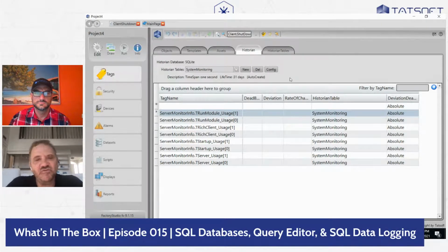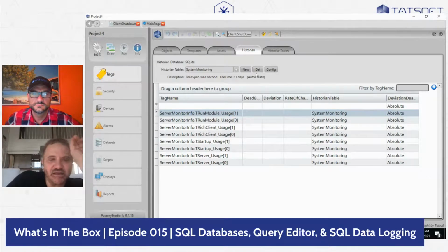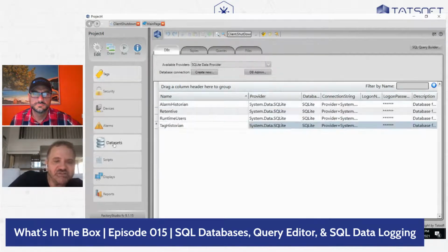And it's very hard to give you a magic number because it depends on how you do your configuration and the hardware. You can get amazingly different numbers on that. So I give you the principles, but not exact numbers. So what should you be aware of? When you do data logging using our own tool, first of all, you have the ability to select where you are going to log. SQLite is good for small projects, a few hundred tags. When you start to go to thousands, you should think about something else.